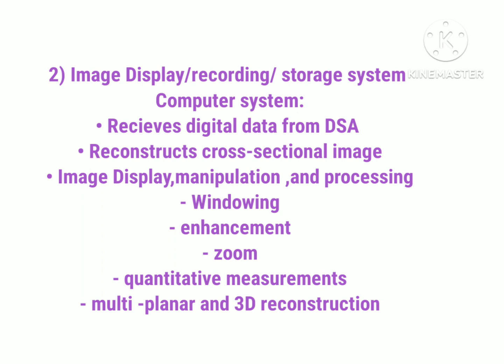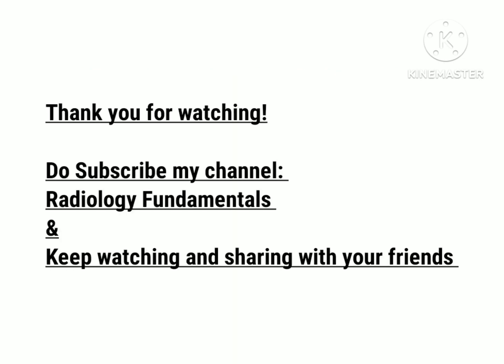Now let's talk about the second major system in CT scanner: the image display, recording and storage system, which is located in the operator's area. The computer receives digital data from DAS and those digital data are reconstructed into cross-sectional images, which are represented on the computer display. These images can be manipulated and processed — windowing can be done, enhancement of the image, zoom, and 3D reconstruction, and much more. This is all about today's topic: components of computer tomography. Thank you for watching, take care.